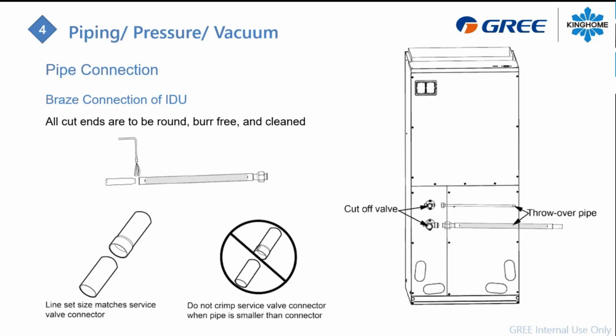The unit comes with flare connections already on the outdoor unit and the indoor unit, so you can use those connections. It's already flared. You can just connect directly on the service valve right here, and then you will have to do a brazing connection right here. So again, flow your nitrogen. It's really important to make a good connection right here.